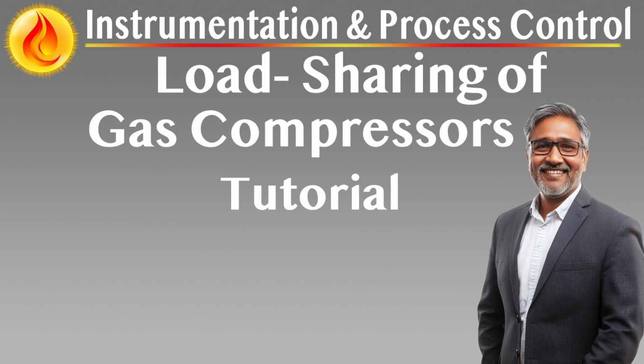Dual response strategy. The role of primary capacity control varies depending on the operating condition of the compressor network. 1. Normal operation, compressors not recycling. The load sharing controller at each compressor receives CRSC. Each controller multiplies CRSC by a designated load sharing gain. The result is added to the controller's integral response, increasing compressor speed or throughput. Anti-surge controllers remain inactive from a capacity perspective in this mode.